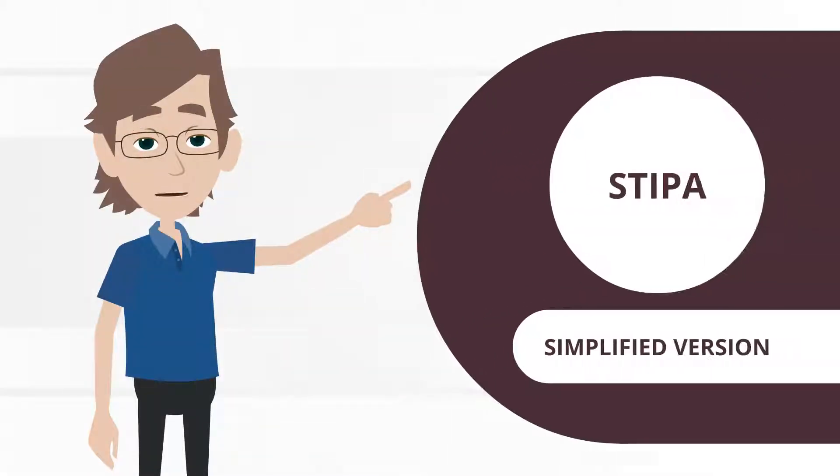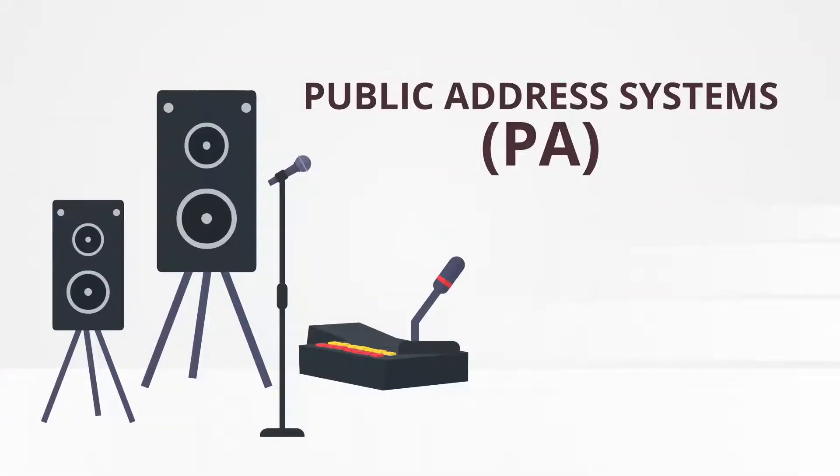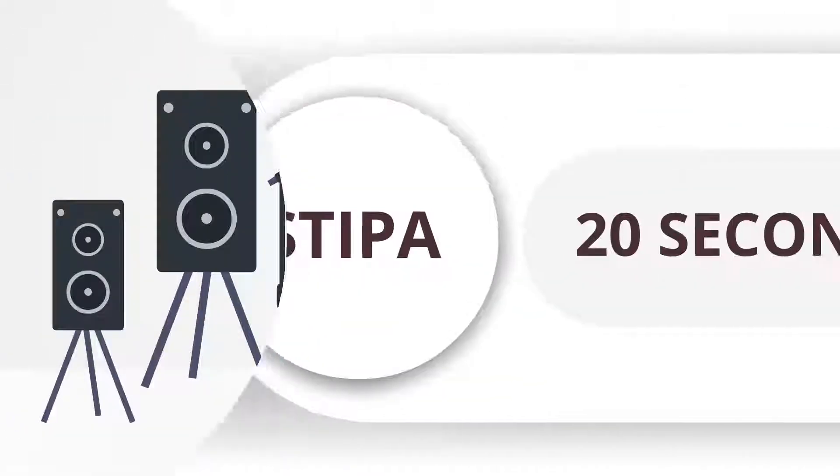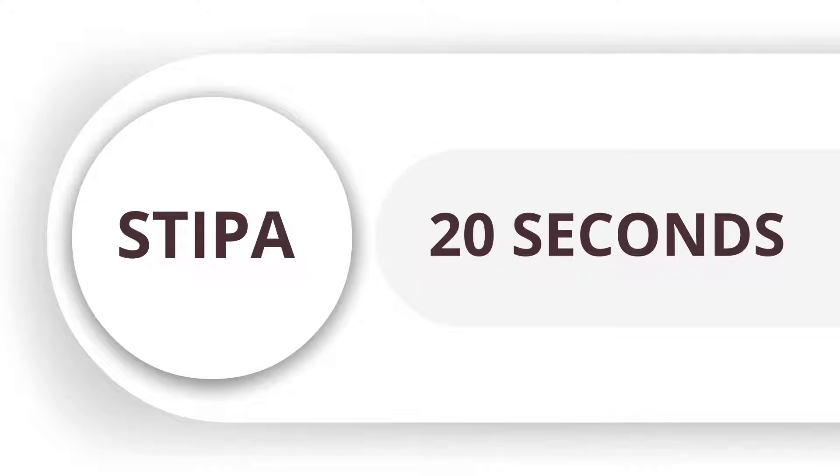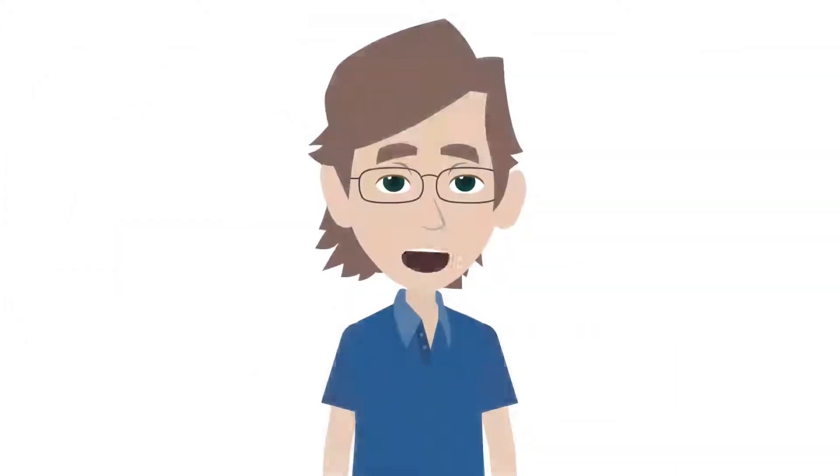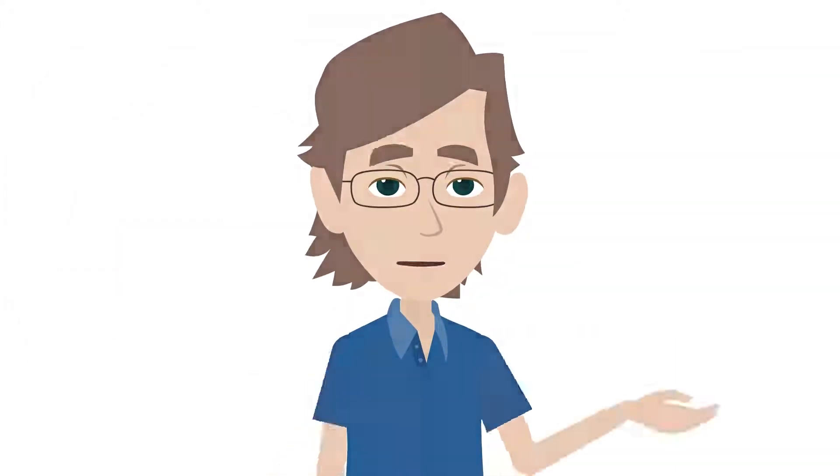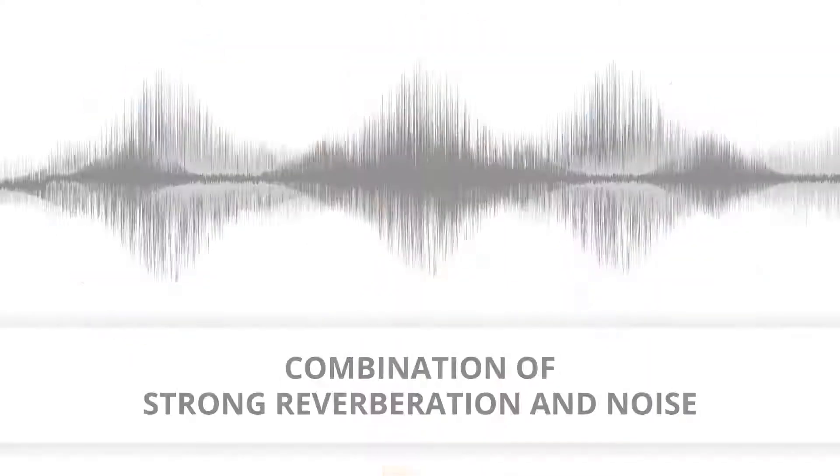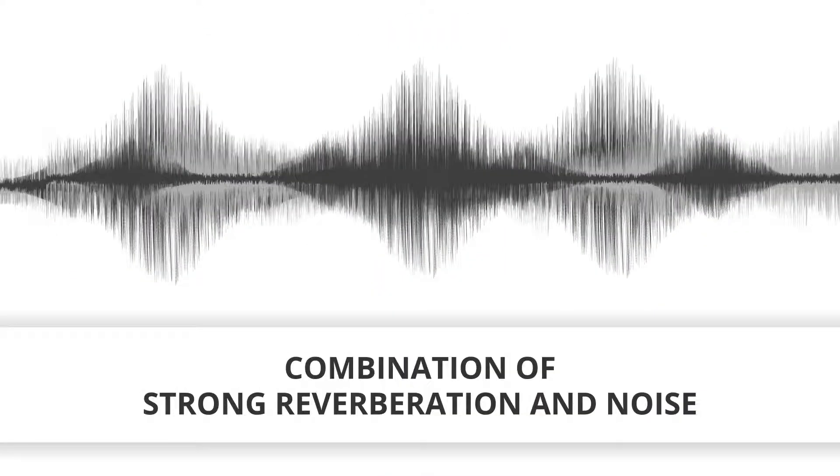STIPA is a somewhat simplified version originally made for public address systems, hence the letters PA. A STIPA measurement only takes about 20 seconds and is just as reliable in almost every situation. Just avoid STIPA if you hear echoes or if you have a combination of strong reverberation and noise.